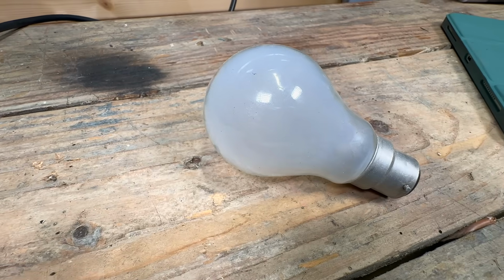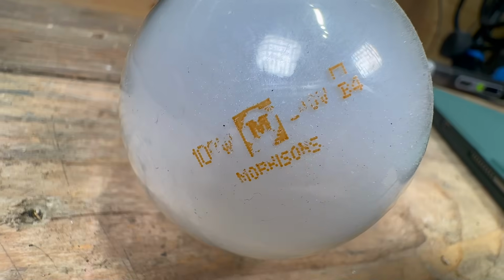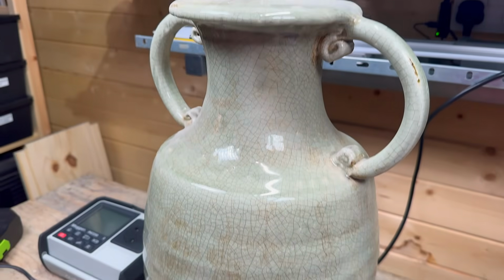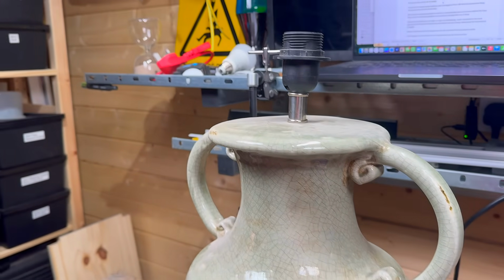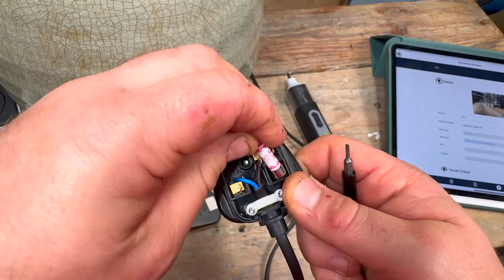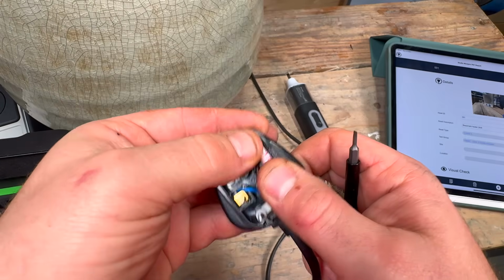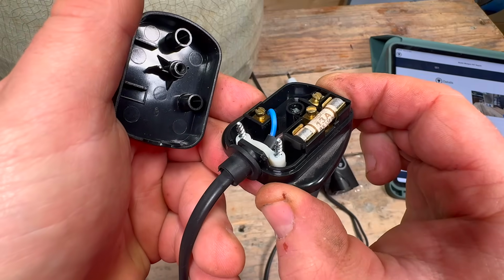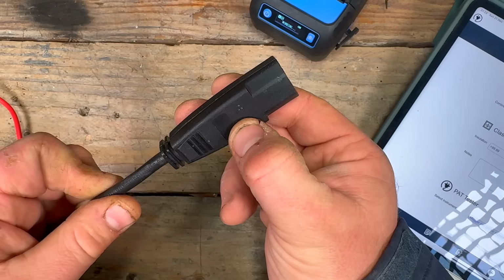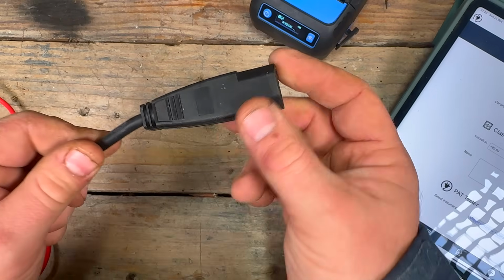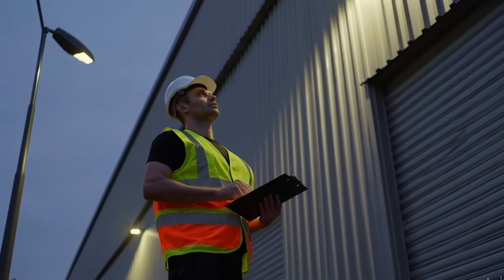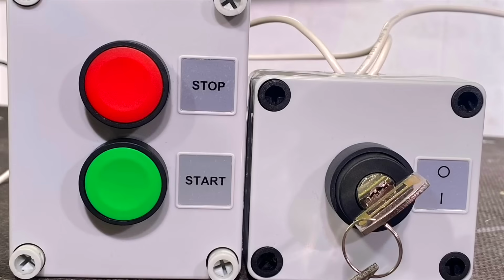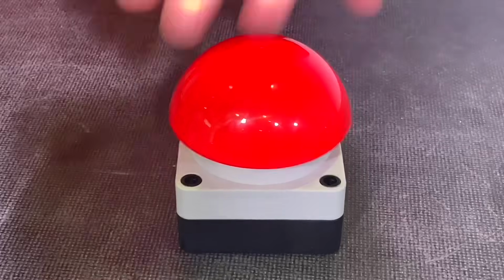If we took the worst case scenario and managed to fit a 100 watt incandescent lamp, this would only be 0.43 of an amp. This means this lamp could be in fault for a considerable amount of time before the fuse blew, and this is not acceptable. Once the fuse rating has been confirmed, we need to check that the connections are tight, there's no sign of overheating, outer insulation in the cord grip, and confirming that electrical connections are not being relied upon for mechanical strength. Next, we need to confirm that the equipment can be switched off and isolated safely. The inspector must identify how equipment can be switched off for normal operations, for maintenance, and in an emergency.